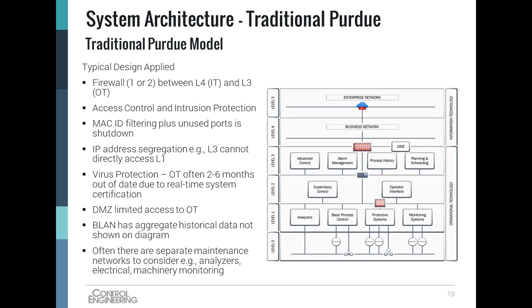So typical designs applied in terms of security - there's typically at least one firewall, sometimes back-to-back firewalls between level 3 and level 4, from the OT to the IT interface. Access control and intrusion protection are traditional methods of security. MAC ID filtering plus unused ports are typically shut down. This limits accessibility to only the devices you're expected to have on the network.